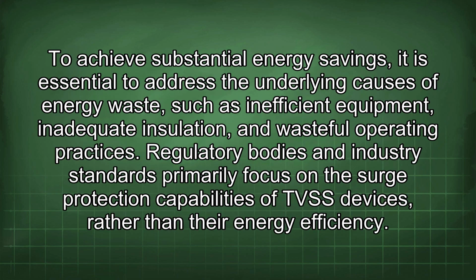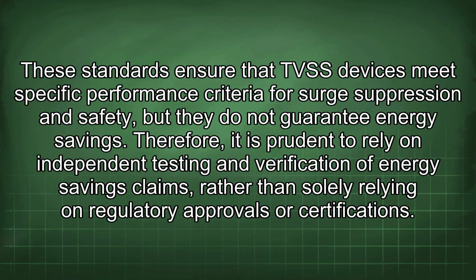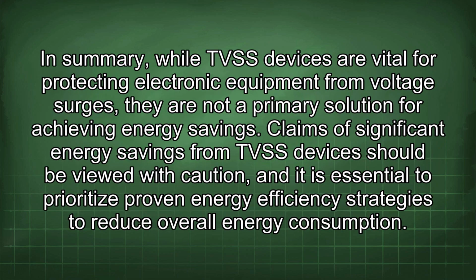To achieve substantial energy savings, it is essential to address the underlying causes of energy waste, such as inefficient equipment, inadequate insulation, and wasteful operating practices. Regulatory bodies and industry standards primarily focus on the surge protection capabilities of TVSS devices rather than the energy efficiency. These standards ensure that TVSS devices meet specific performance criteria for surge suppression and safety, but they do not guarantee energy savings. Therefore, it is prudent to rely on independent testing and verification of energy savings claims rather than solely relying on regulatory approvals or certifications. In summary, while TVSS devices are vital for protecting electronic equipment from voltage surges, they are not a primary solution for achieving energy savings. Claims of significant energy savings from TVSS devices should be viewed with caution, and it is essential to prioritize proven energy efficiency strategies to reduce overall energy consumption.